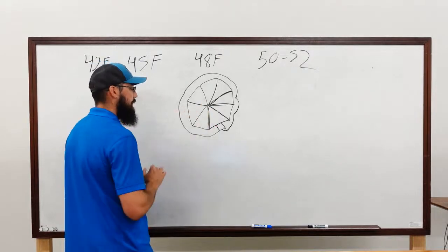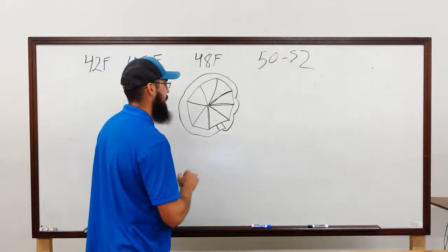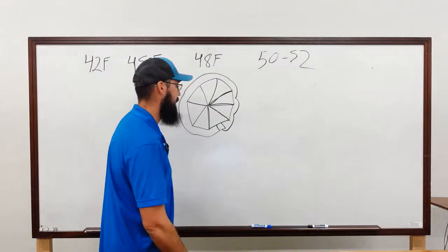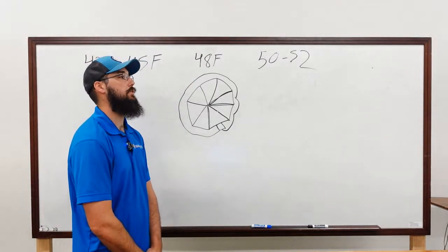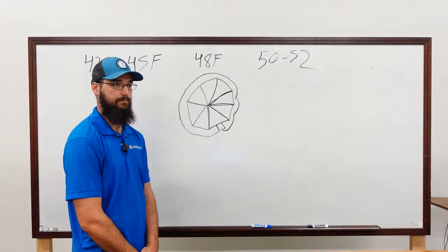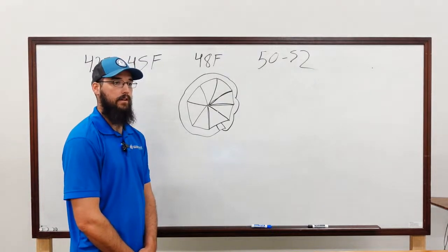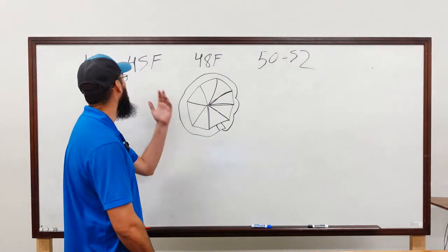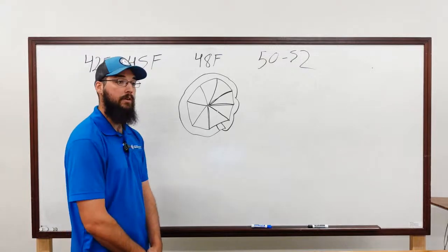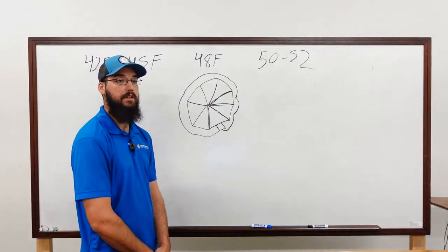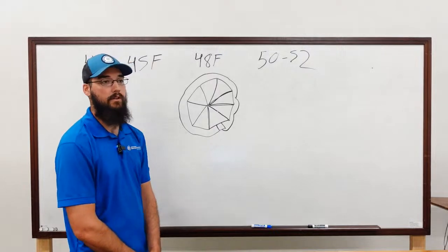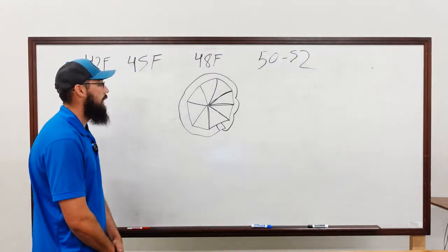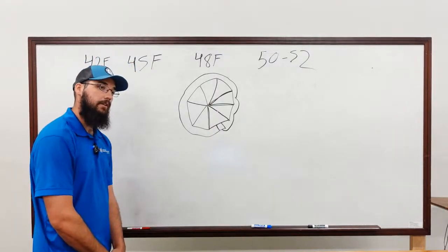By modern standards, you might walk up to a machine and see that the IGV is wide open, 100%, and it's maintaining a set point just fine. And say you've got 50 degree entering water. There's no reset or anything on the system. So that seems kind of weird, right?